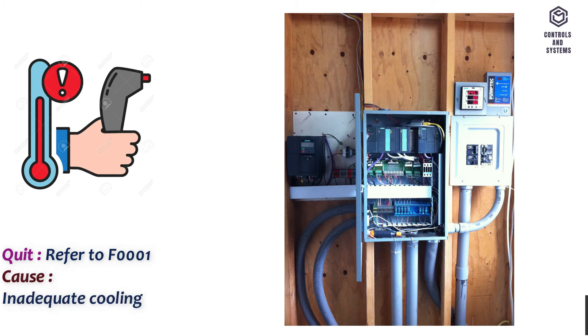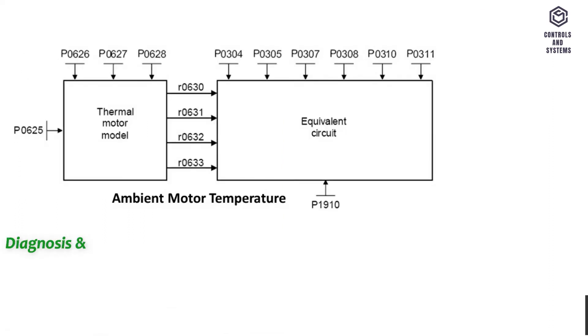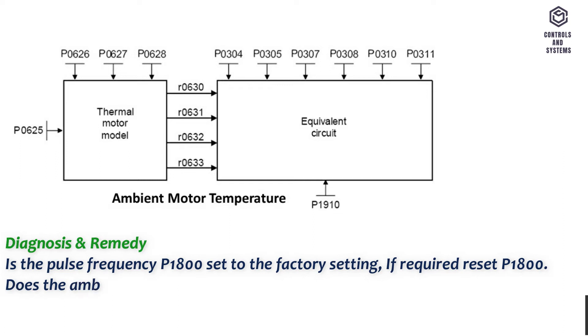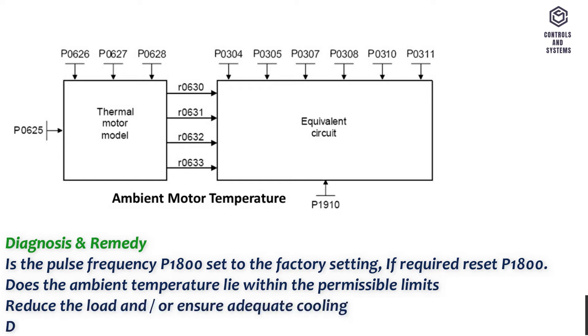Inadequate cooling. Ambient temperature is too high. Diagnosis and remedy: Is the pulse frequency P1800 set to the factory setting, if required reset P1800? Does the ambient temperature lie within the permissible limits? Reduce the load and/or ensure adequate cooling. Does the fan rotate if the inverter is operational?